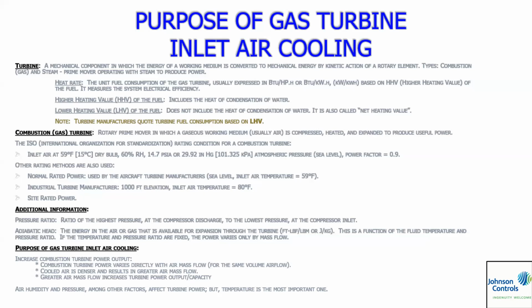Okay. Additional information, just some definitions for the college folks that might be joining us. Pressure ratio is the ratio of the highest pressure at the compressor discharge to the lowest pressure at the inlet. Adiabatic head is the energy in the air or the gas available for expansion through the turbine. It's a function of fluid temperature and pressure ratio. Those are fixed. The power varies only by mass flow.